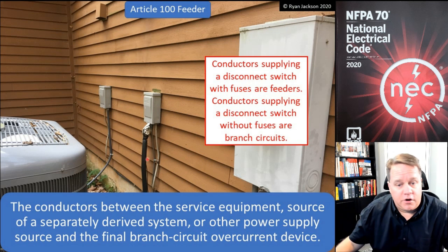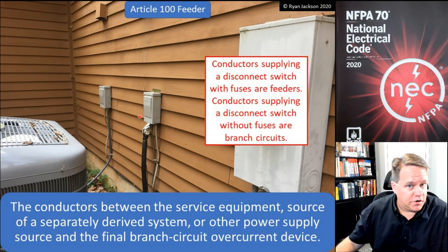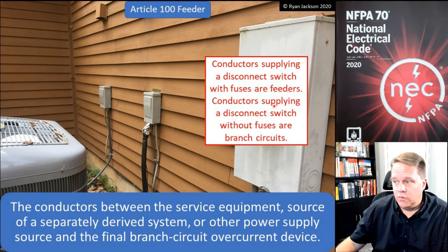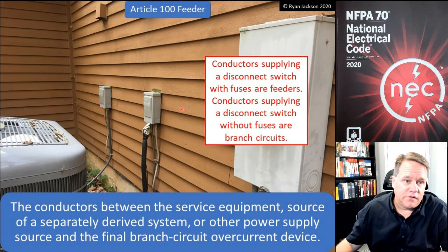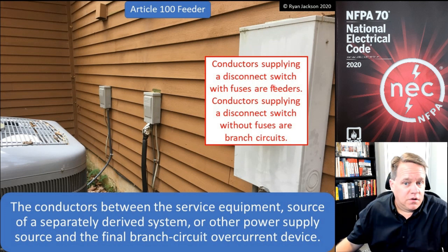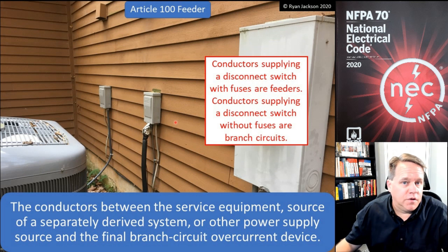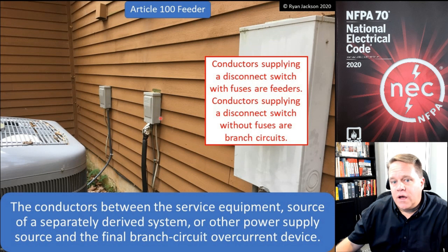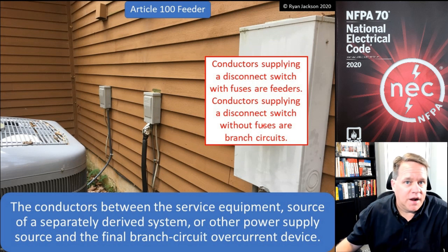Here I've got a panel board on the right and some disconnects for my air conditioners. Is the run from the panel to the disconnect a feeder circuit or a branch circuit? It starts at a breaker or fuse, so it's either one. What does it end at? If it ends at a breaker or fuse, it's a feeder. But if these disconnects don't have fuses — say it's just a pull-out disconnect — then this would be a branch circuit, starting from the panel, feeding the non-fused disconnect, and going through to the utilization equipment.